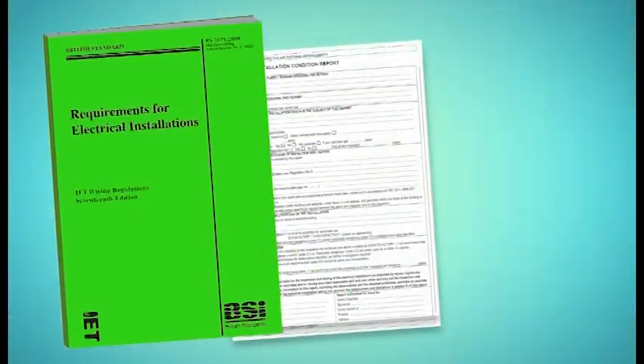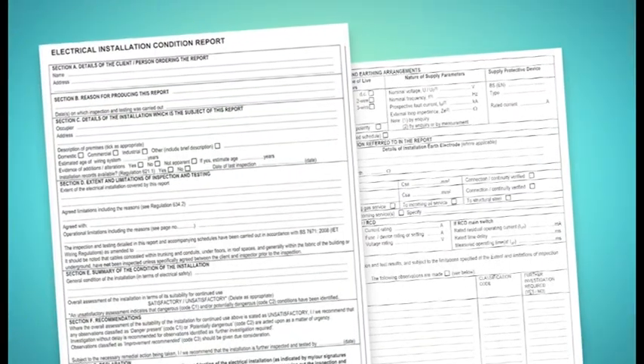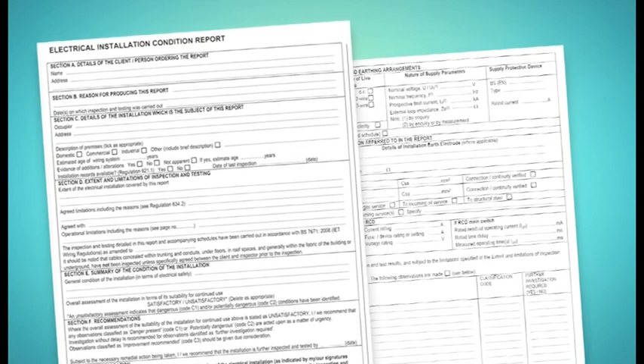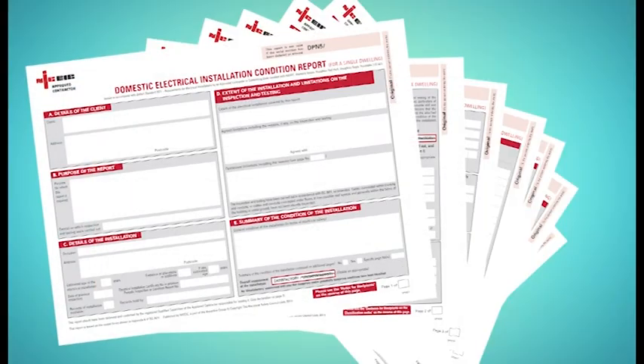Now, an example of an electrical installation condition report can be found in the model forms in Appendix 6 of the 17th edition, and these forms are actually perfectly fine to use. However, there are refined versions available. With the NICEIC forms, you'll find some additional information will be required, which should make it more user-friendly. And it's interesting to point out that the NIC domestic report has gone from 4 pages to a minimum of 7. Okay, TC, let's get on site.